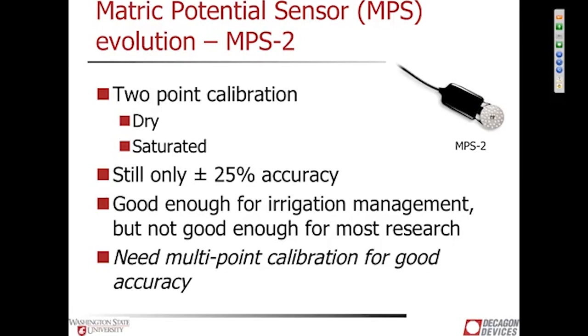but it's not going to be good enough for most research. And you know, when we published the 25% accuracy spec, we took a lot of heat from our research friends saying, why is this so broad? Why is this such a bad accuracy spec? And we said, well, it's because we publish an accuracy spec. If you look at any of the other porous matrix sensors out there, none of them publish an accuracy spec, and there's a good reason for that: this is not an easy measurement to make.